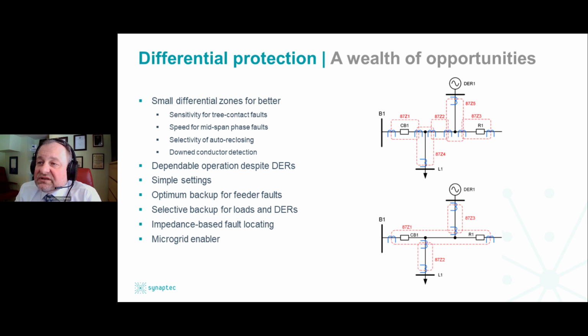So regardless of which zone detects a fault, I am still going to trip the CB1 at the substation and recloser 1 somewhere along the feeder, and I may send direct transfer trip signals to the DER if located or connected to that tripping zone. Small differential zones give me better sensitivity, better speed, better selectivity. The CTs allow me to detect down conductors. Differential protection is dependable despite the DERs and their unusual fault response. They have very simple settings. I would argue that you could run them with default settings.